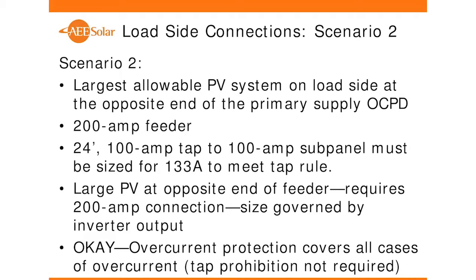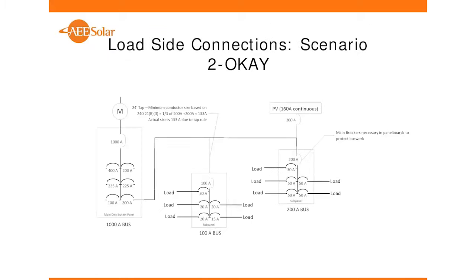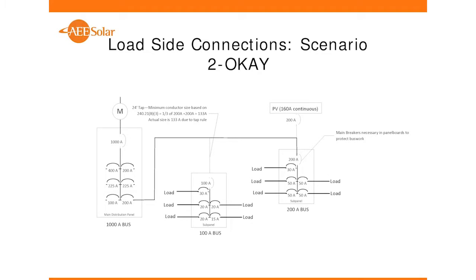So let's talk about the 25-foot tap. Now, with the 25-foot tap, we've got to go to 1/3, and it's 1/3 of the feeder breaker plus the PV, and that creates a little bit different story because the tap is longer. The minimum ampacity of that conductor is not 100 amps. What overrules is 400 divided by 3, which is 133 amps. Now the likelihood that that 25-foot tap is already 133 amps is probably small. You have to calculate it, see what the ampacity of an existing conductor would be, and if it was not acceptable, you would either have to upgrade that tap to a 133 ampacity conductor, or you would have to move. The simpler way to do it would be to put an overcurrent device right there, within 10 feet of the tap. Because if you're within 10 feet of the tap, then the 10-foot tap rule would govern.